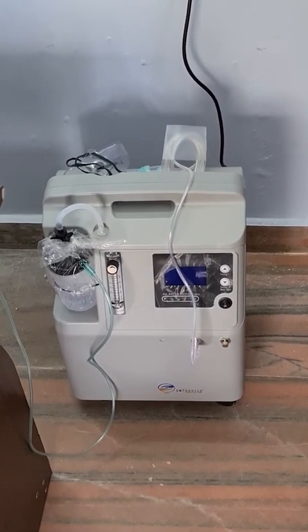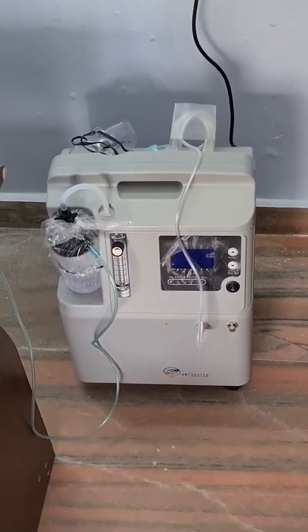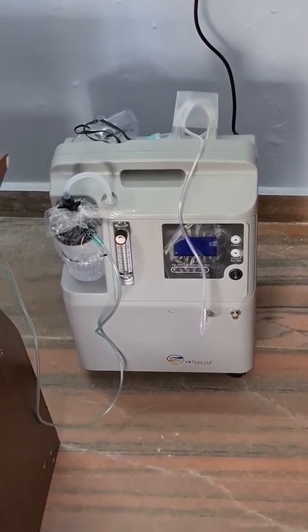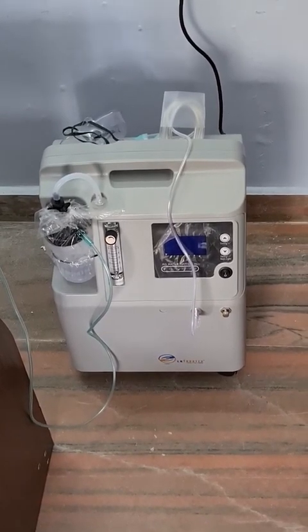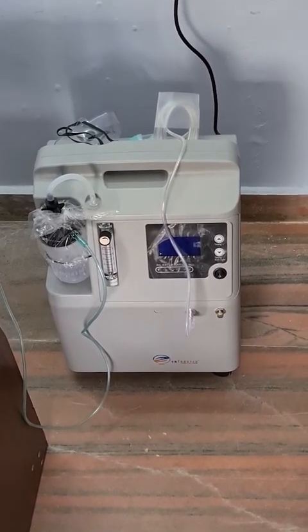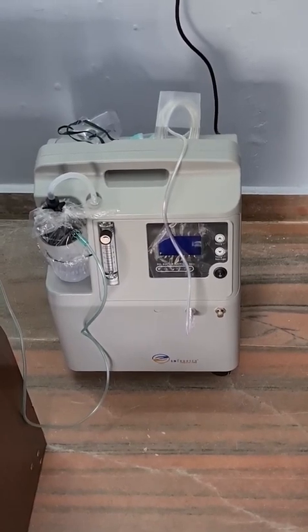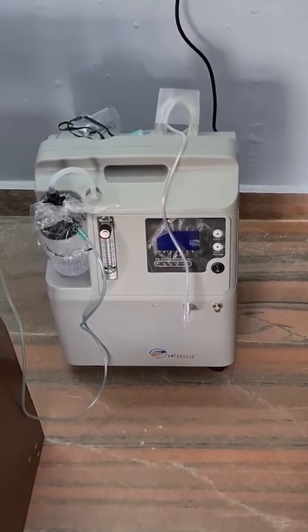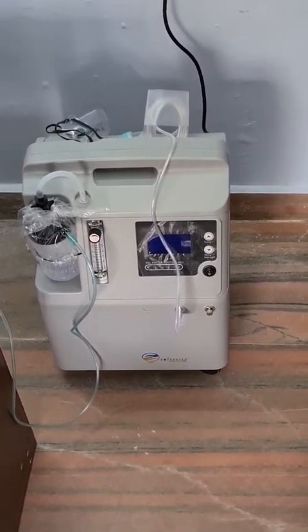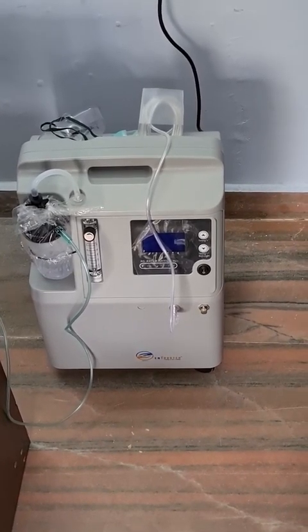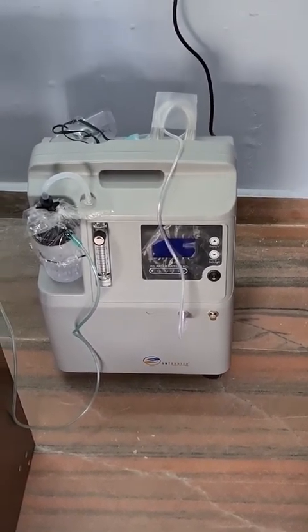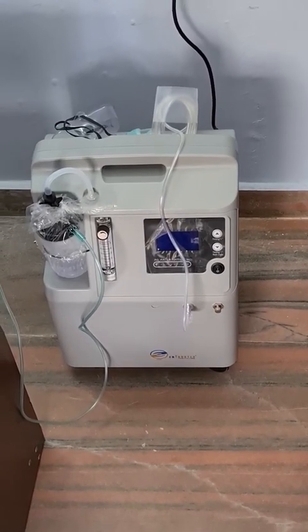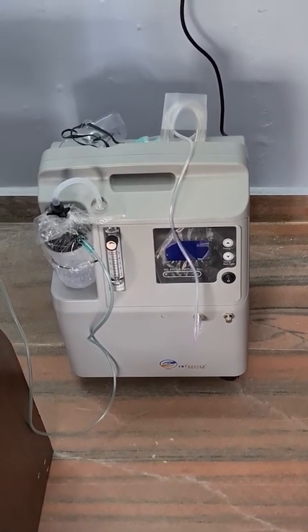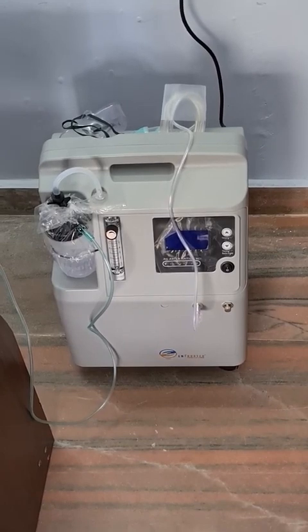Another main thing: you need to use this machine either as a concentrator or as a nebulizer. When you are using it as a concentrator, adjust the flow rate to whatever level you want and make sure the nebulizer port is closed. When you want to use nebulization, bring the oxygen flow knob to 0 and then switch on the nebulizer port. Always remember, do not keep both of these at 0. Either one of them should be switched on.